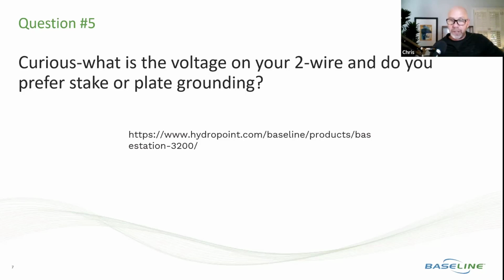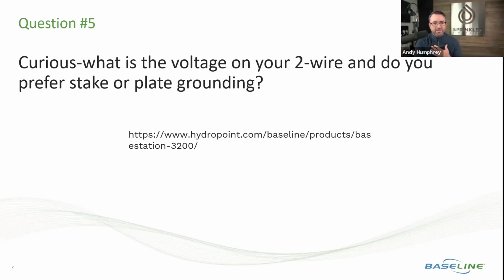Preferably 10 ohms or less. So I'd say we care about the ohms of resistance. The project or the engineer or the consultant may care what is being used, because that might be their personal preference. But if all it takes, I'm making this up, is a 5-foot ground rod to meet that, say 15 ohms, it's not that it's one plate or 2 plates or 2 rods or a plate and a rod. It's really just trying to obtain that resistance.